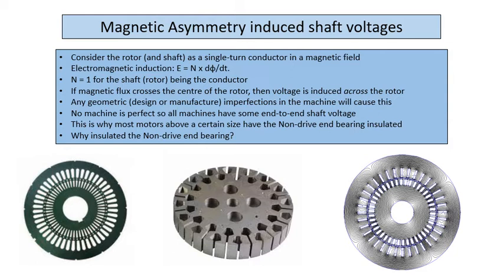And your magnetic asymmetries can be designed in or manufactured. Like I showed you a few, where that's a design that will have an effect on shaft voltages. And then, okay, this is why most motors above a certain size have the non-drive end bearing insulated. Why? To break that current path. So your current will want to circulate through the frame of the motor from one end to the other via the bearings. So you insulate one bearing and you break that current path.